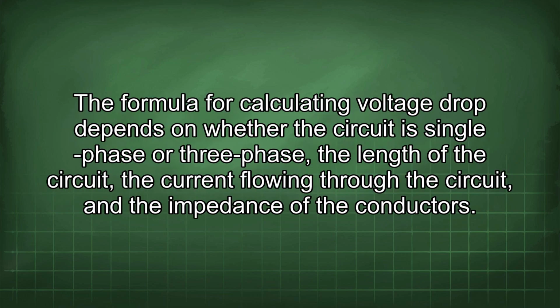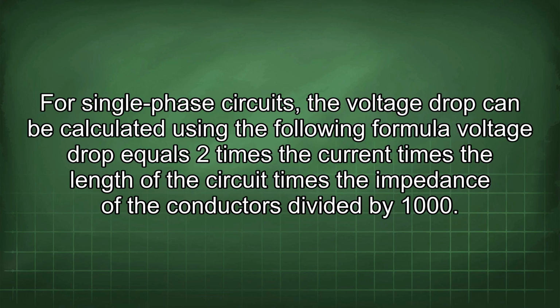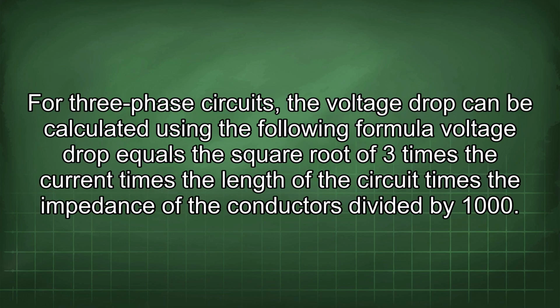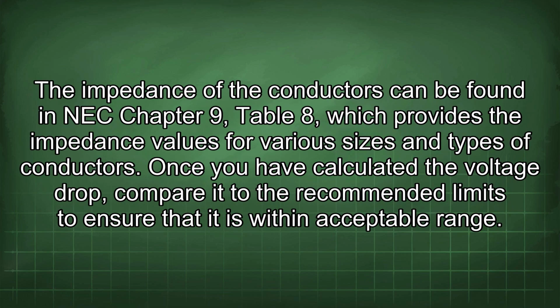The formula for calculating voltage drop depends on whether the circuit is single-phase or three-phase, the length of the circuit, the current flowing through the circuit, and the impedance of the conductors. For single-phase circuits, the voltage drop can be calculated using the following formula: voltage drop equals 2 times the current times the length of the circuit times the impedance of the conductors divided by 1000. For three-phase circuits, the voltage drop can be calculated using the following formula: voltage drop equals the square root of 3 times the current times the length of the circuit times the impedance of the conductors divided by 1000. The impedance of the conductors can be found in NEC Chapter 9, Table 8, which provides the impedance values for various sizes and types of conductors.